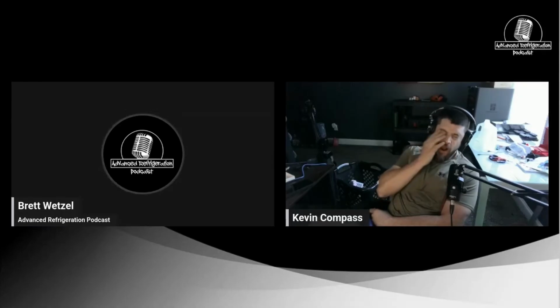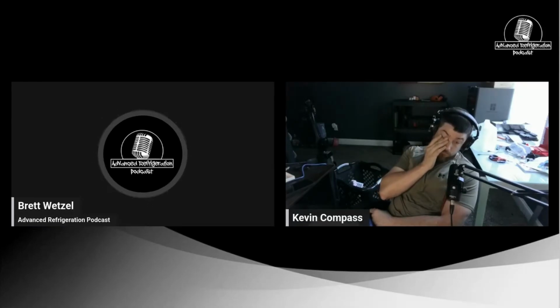No, I mean, like I said, this guy called me last week, and they were having issues with the rack. I said, what kind of discharge temperature do you have on all your compressors? Because as well as I do, a pump down test doesn't really tell you much. Nope. Using the Bitzer online app or the Copeland mobile app tells you what the discharge temperature should be. So that's what he did. He went to the Bitzer online, he calculated what the discharge temperature should be. It was a lot more elevated than what it should have been.